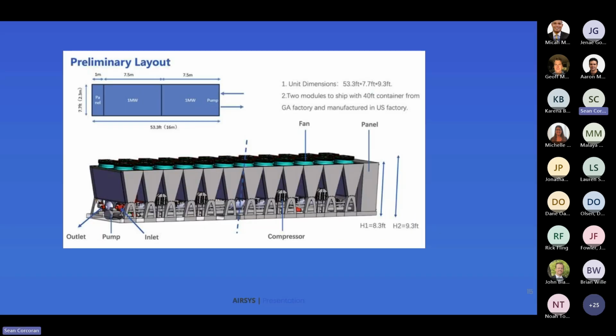The dimensions of our 2 megawatt or 504 ton chiller: we're going to be doing this in a 53 foot footprint, if not a little bit smaller, as we continue to look at other designs. It's going to be a height of no more than 9 feet and a width of no more than 7.5 feet wide. What this does is give us the ability to deploy faster, and the ability to not have escort type of trucks when we ship, because it will fit on a 53-foot truck. And at the end of the day, when it arrives at site, there'll be lower connections or easier connections for the mechanical contractor to install the product.